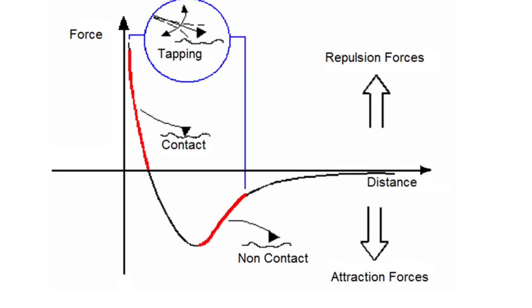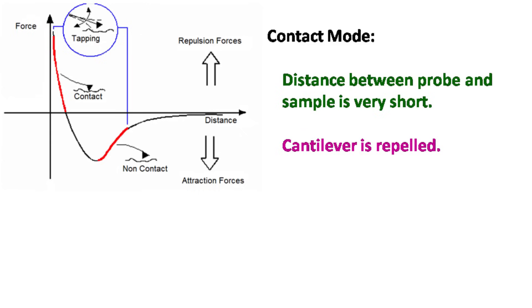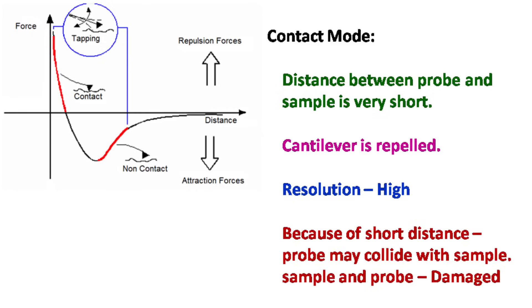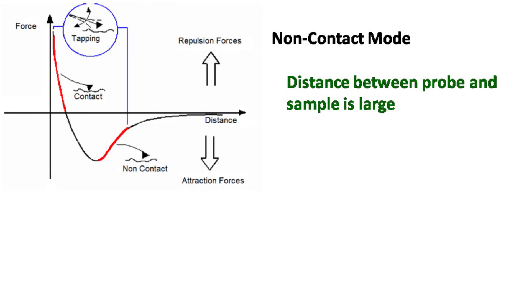In contact mode, the distance between the probe and the sample is kept very small. As a result, the cantilever is repelled. The resolution obtained by this mode is very high. However, because of the short distance, the probe may collide with the sample and damage it.